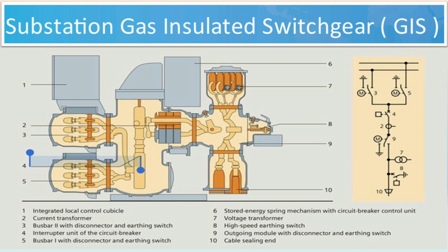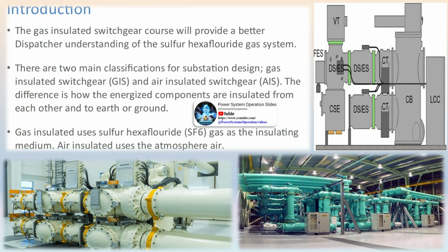What is a gas-insulated substation? A gas-insulated substation, GIS, is a high-voltage substation in which the major conducting structures are contained within a sealed environment with a dielectric gas known as SF6, or sulfur hexafluoride gas, as the insulating medium. In comparison, in a conventional AIS, or air-insulated substation, atmospheric air is the dielectric gas medium, as these types of substations are almost always located at outdoor locations.